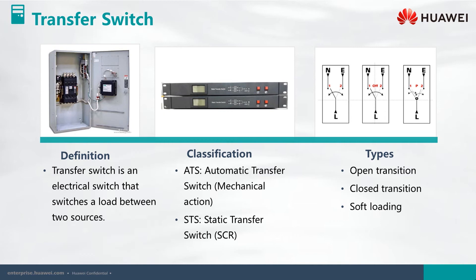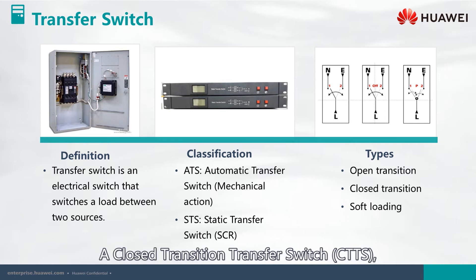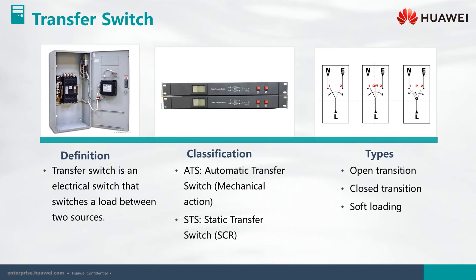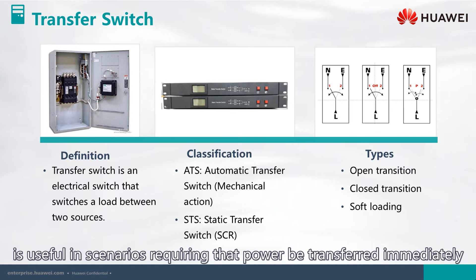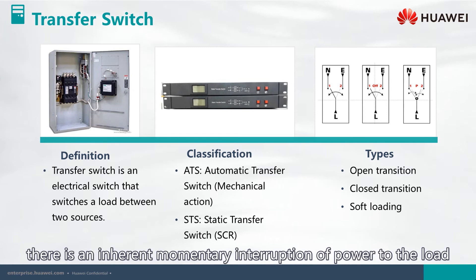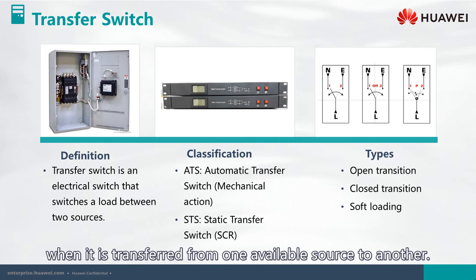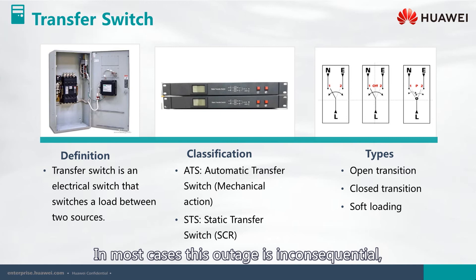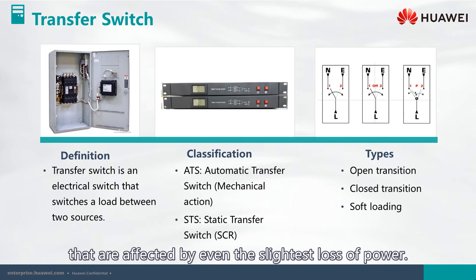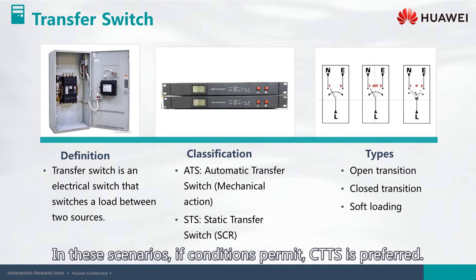A closed transition transfer switch, CTTS, also known as a make-before-break transfer, is useful in scenarios requiring that power be transferred immediately following a power interruption. In a typical emergency system, there is an inherent momentary interruption of power to the load when transferred from one source to another. In most cases this outage is inconsequential, particularly if it is less than one-sixth of a second. However, some loads are affected by even the slightest loss of power, and in these scenarios, if conditions permit, CTTS is preferred.